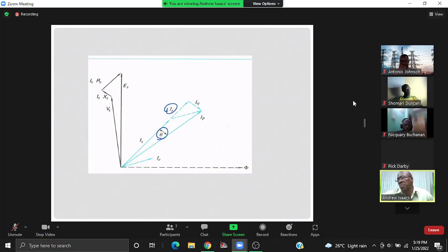So in other words, there are times when instead of specifying current error, which we just spoke of, which is IR, and also phase error, which is given by IQ or theta, we can speak of composite error, which is looking at the magnitude, which is the difference between the actual and the ideal, the current and phase errors, and also harmonics.